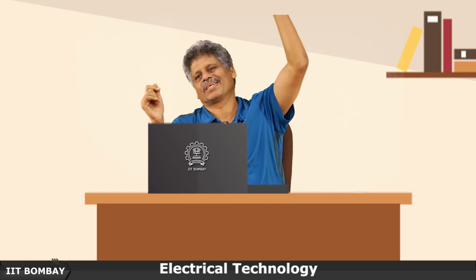Usually I have not mentioned this in the course, but I'll mention it here: when a utility buys a transformer, say a 3-phase transformer, it also specifies how much leakage reactance it wants, like 8% or 10% on its own rating. This is because if the leakage reactance goes very low and by mistake a short circuit happens, the short circuit current will go very high, which could be a problem. So to control short circuit current, a utility may specify while buying that it wants approximately so much leakage reactance, and then the designers will handle that.